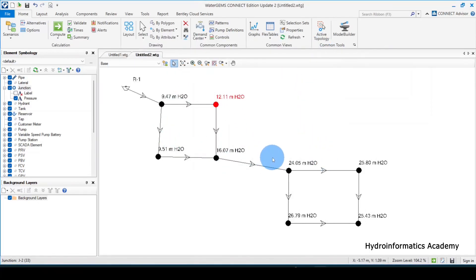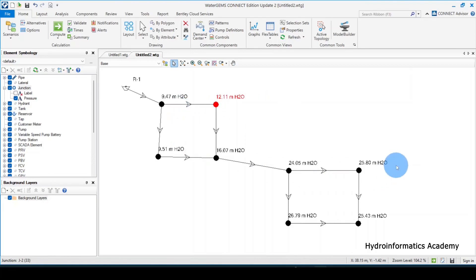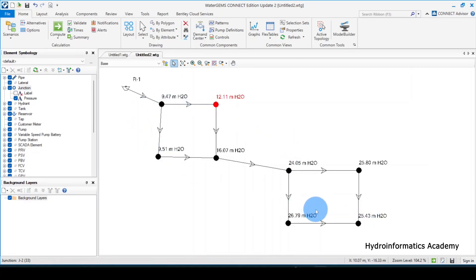You can see the updated pressure values. Around these areas, we don't have a lot of problems with pressure. For most water distribution systems, it is advised to have at least 10 meters of water column up to 30 — or sometimes as low as 6, depending on the country. The current pressure values are within acceptable range and not above 3 bars or 30 meters of water column, so we'll maintain the model as is.